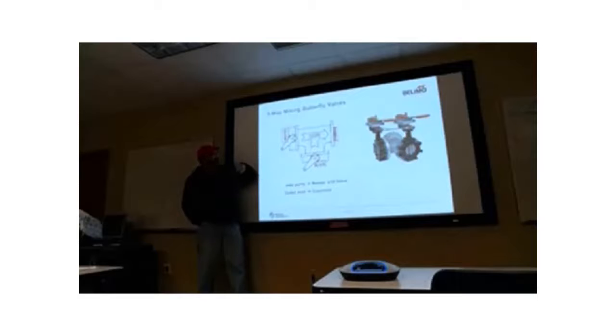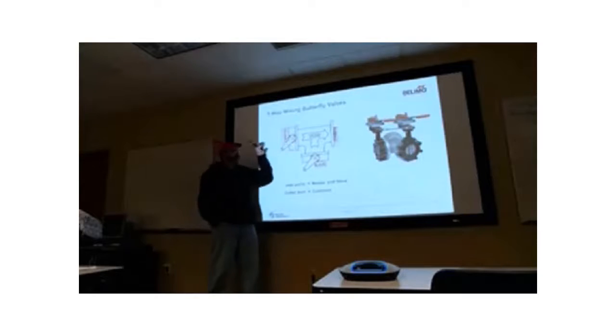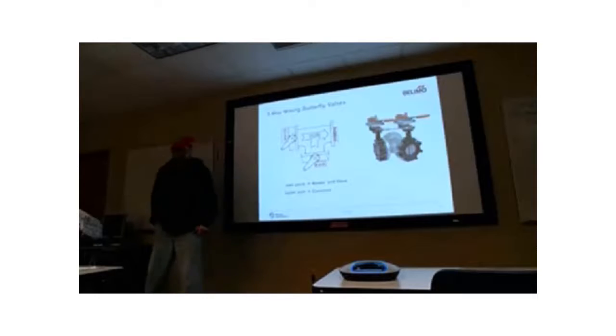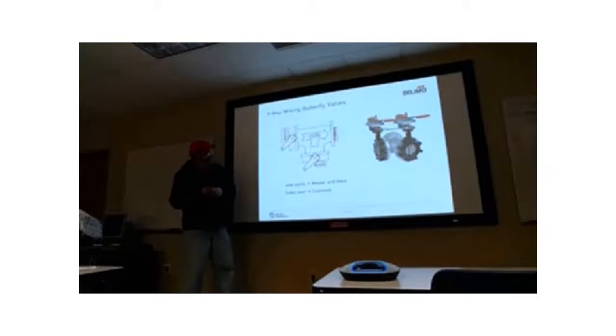So when we define how the butterfly valve is set up, we call the master valve, and the master valve is always on the run. Talking about the through path of the T, right? So anytime whatever valve is on the run across through the valve, it's called the master valve, and this is called the slave. Now if you look over there, you can see, well, wait a minute, John, okay, one's a master, one's a slave, but it's got two actuators and one's on each valve.